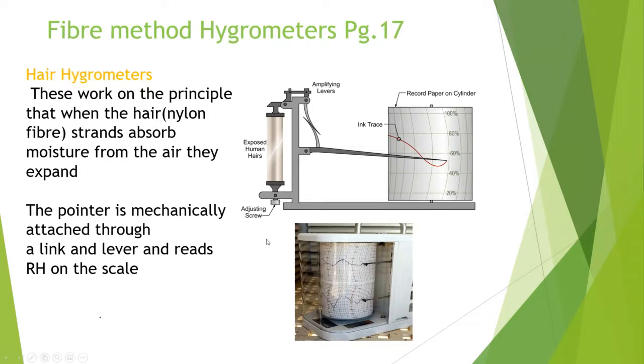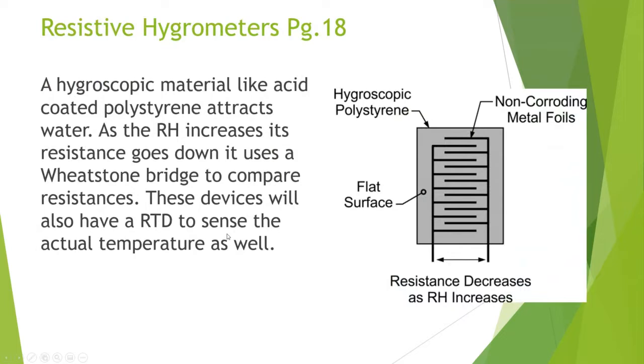The pointer is mechanically attached through a link and lever system. In fact, when visiting a museum in Montreal, a hair hygrometer from the 1800s made of oak was still in use to measure the moisture content of the room. The second type is a resistive hygrometer — an electronic style relative humidity measuring device. A hygroscopic material, specifically an acid-coated polystyrene, attracts water. As relative humidity increases, the material absorbs more water, becomes more conductive, and resistance goes down.